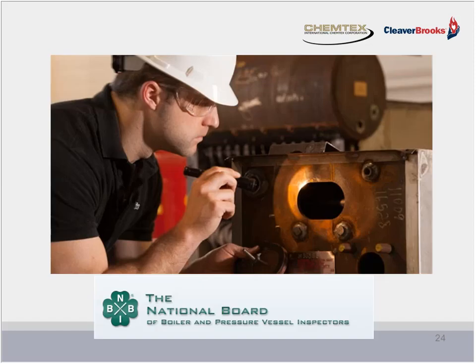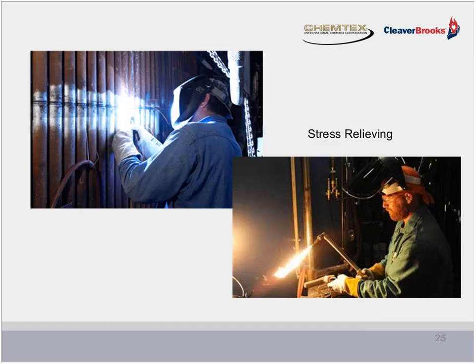And also understand that any field repair of this type needs to be inspected and approved by a qualified inspector who is sanctioned by the National Board of Boiler and Pressure Vessel Inspectors, who require specific and rigid standards and procedures that they be followed or the repair will not be approved. This includes specific weld material, depending on the repair, be it a tube, tube to ligament attachment, furnace repair, and so on.